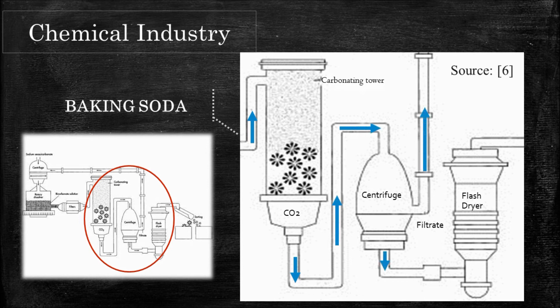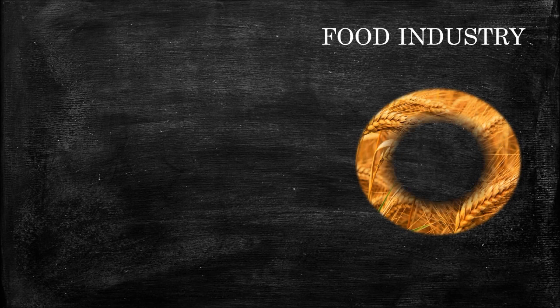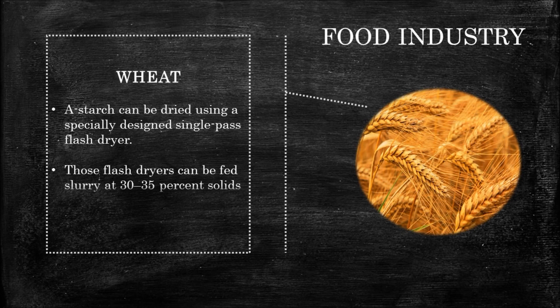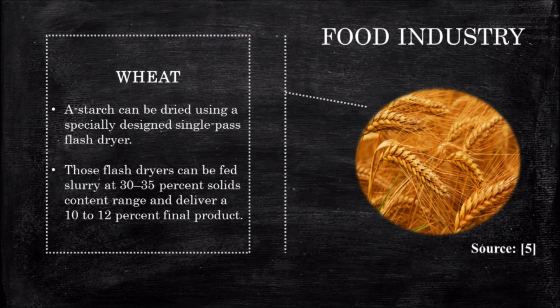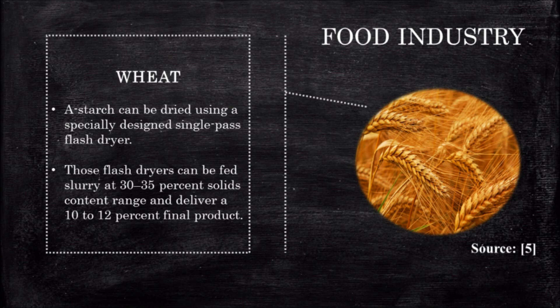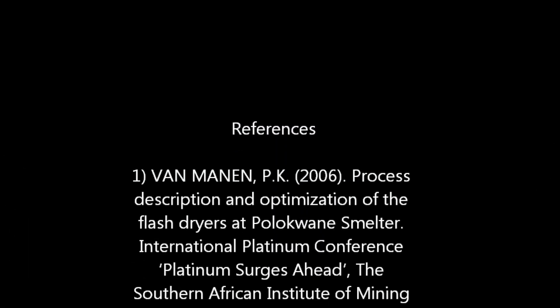In the food industry, starch can be dried using a specially designed single-pass flash dryer. Those flash dryers can be fed slurry at 30-35% solids content range and deliver a 10-12% final product.